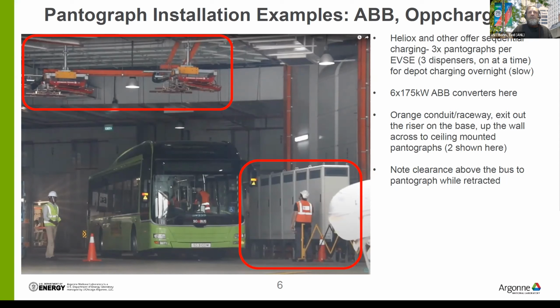On the right, where you see the person standing behind the temporary barricade with the orange vest, the lower right red box are the power converters. You can see a whole row of power converters, all just to feed the overhead charging station. At 600 kilowatt you need about 4 to 6 cabinets, depending on how power dense they are. You can see a black or dark gray riser, where the power conductors enter and exit this particular setup, so they're not cast in concrete but added on after the building into the building space.